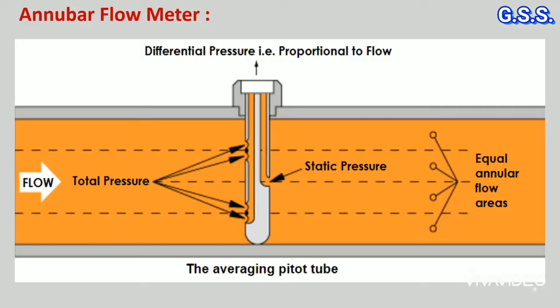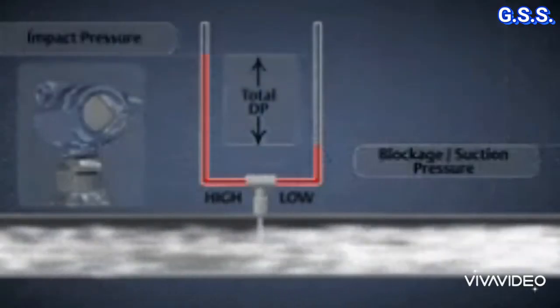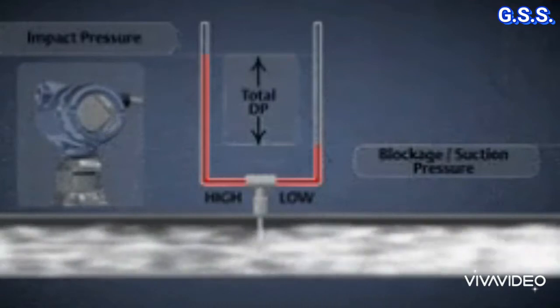Working principle of pitot tube and annubar is almost the same. The only difference is annubar takes multiple samples across the pipeline, and annubar averages the differential pressure for variation of flow across the pipeline.